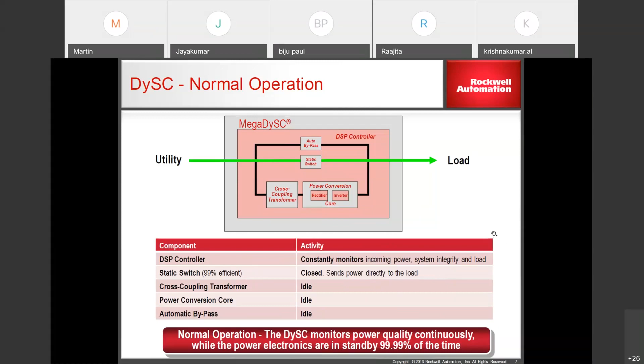The static switch is 99% efficient. It is in closed condition during normal operation, and sends the power directly to the load. The cross coupling transformer is idle. The power conversion core is idle. The automatic bypass is also idle in this case. You can see that while the power electronics is in standby mode, 99.999% is the efficiency we are talking about in this condition.